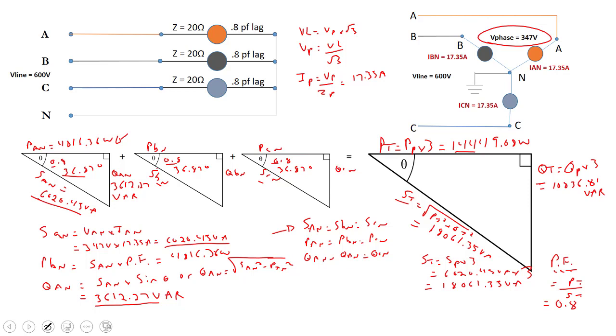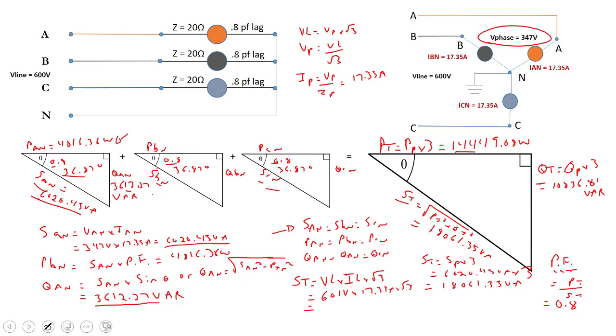I can add up all apparent power values at their angles to get the total apparent power. Now I'm going to introduce a new formula: S total equals V_line times I_line times root 3. Plugging in the values — 601 volts times 17.35 amps times root 3 — gives 18,061.35 VA. Same value. So we've got a second formula that works here.